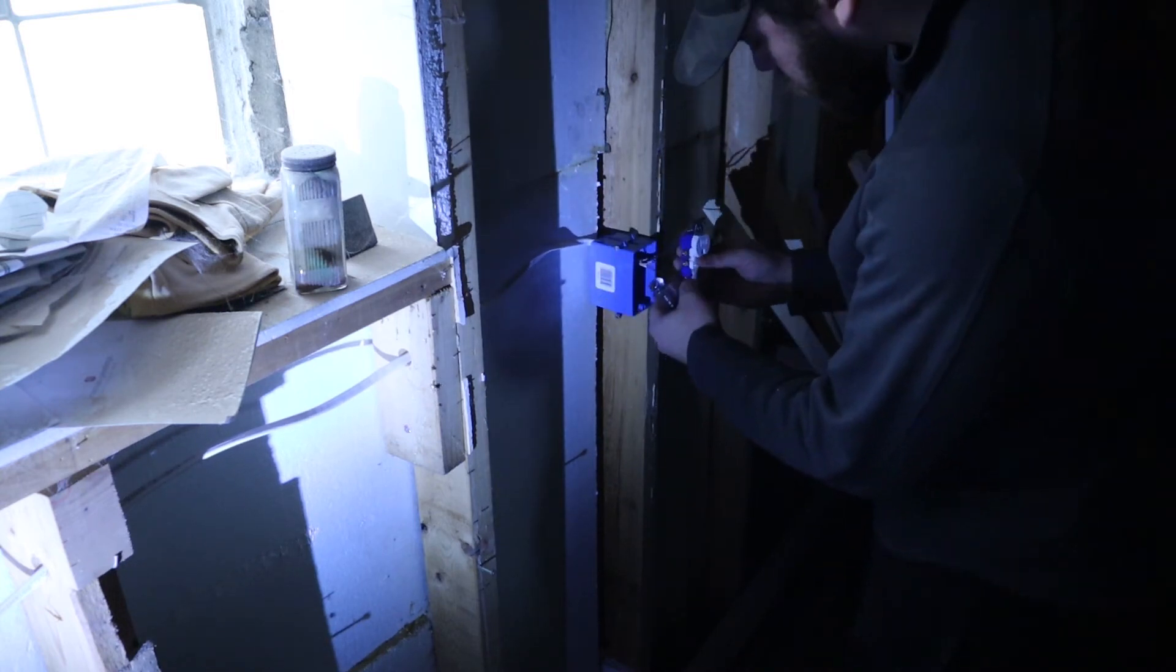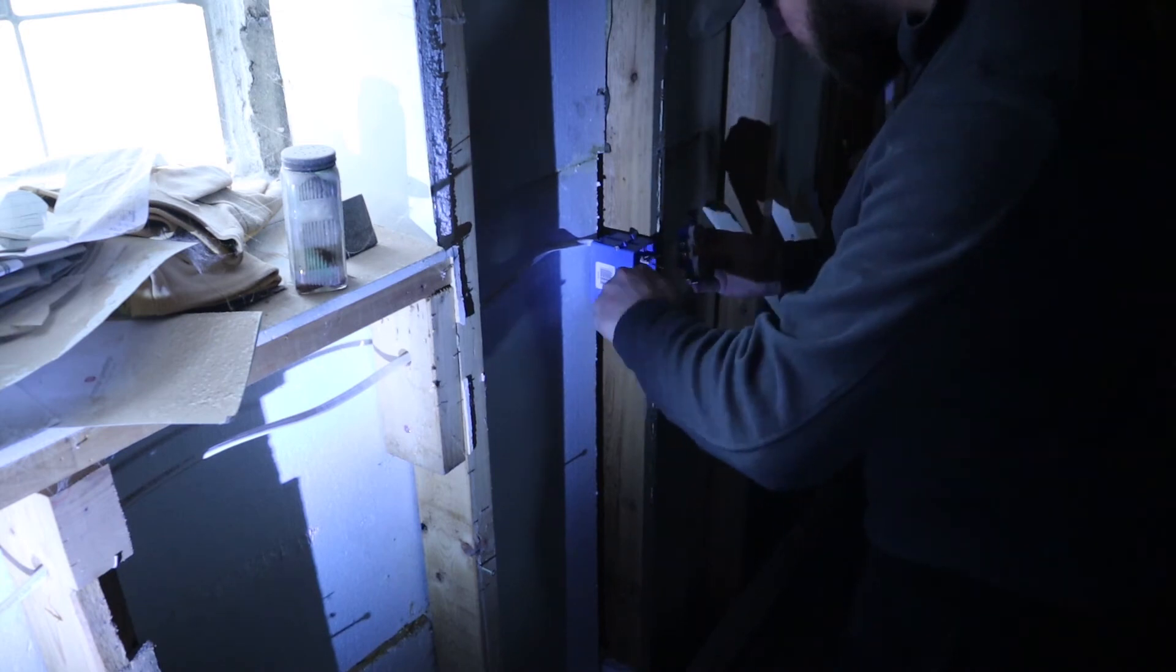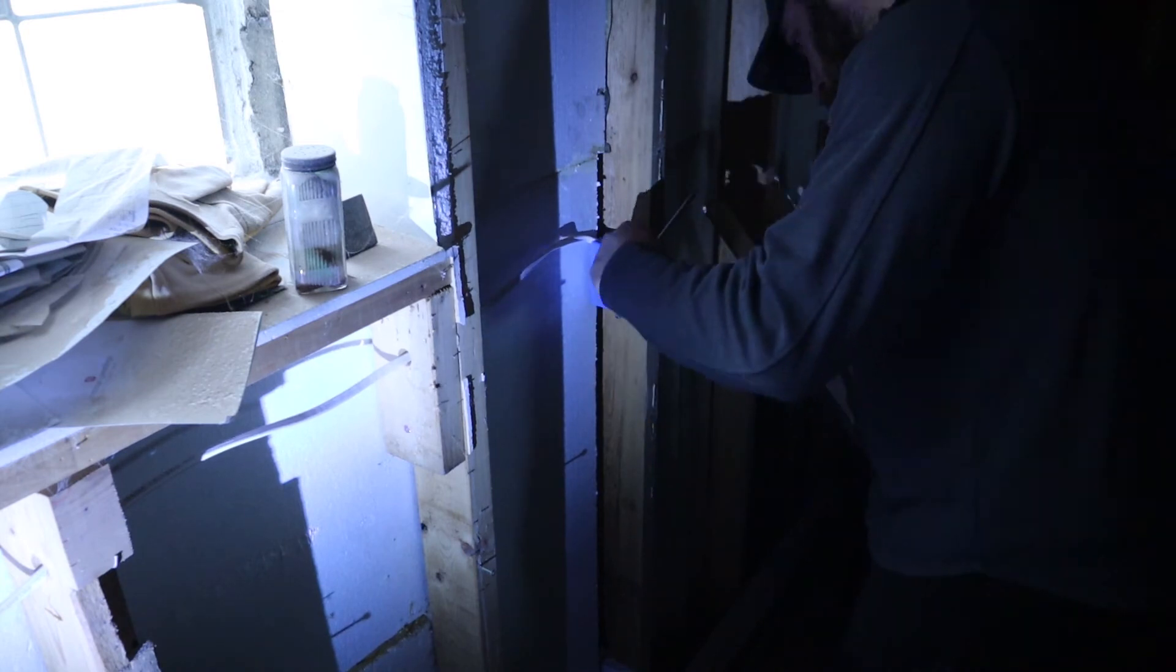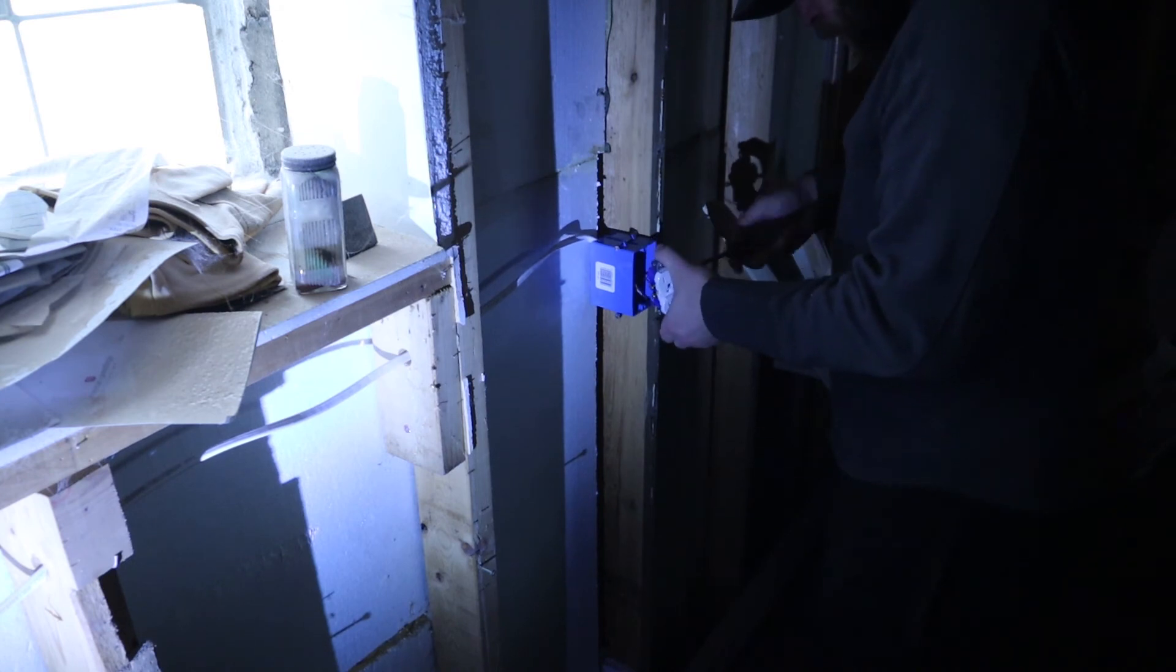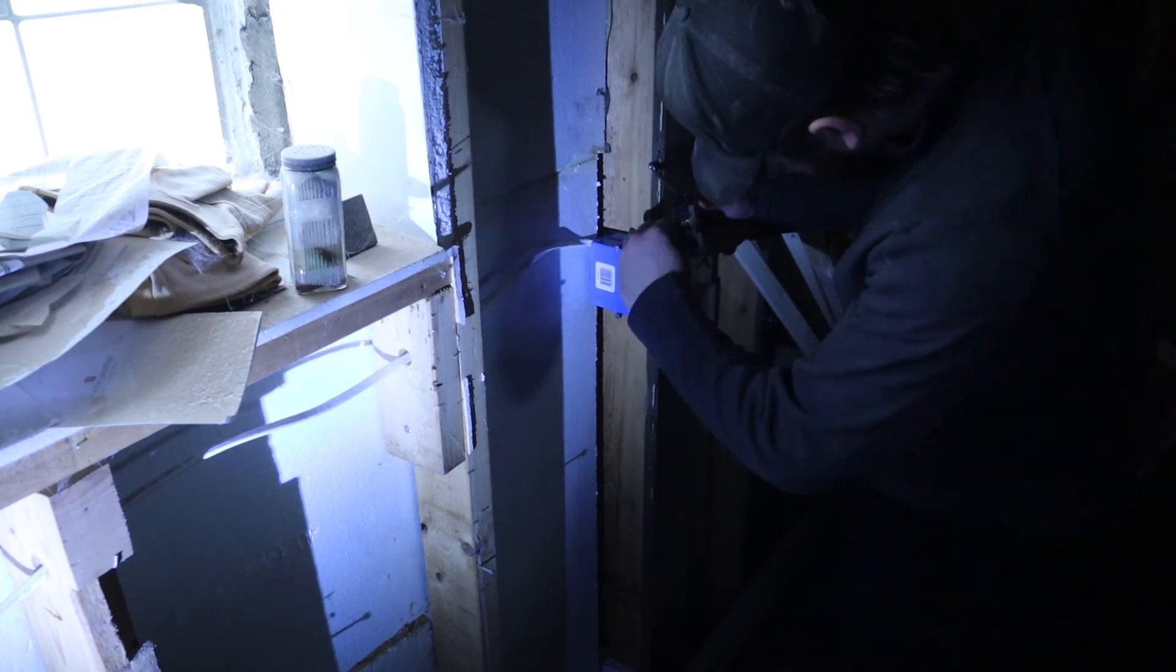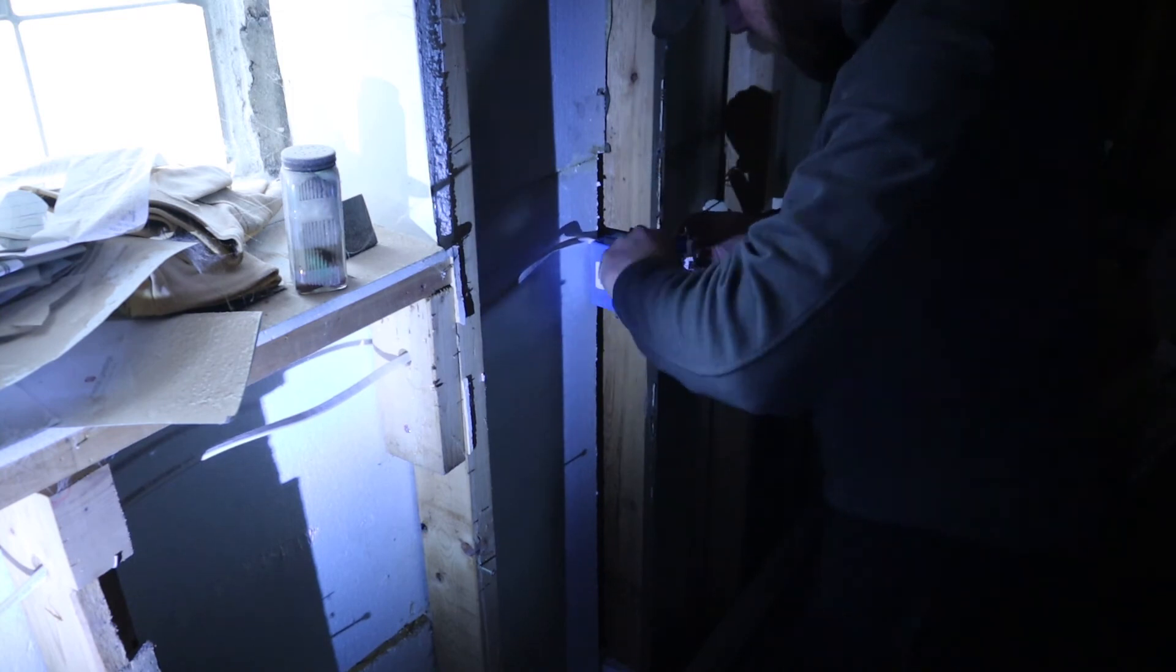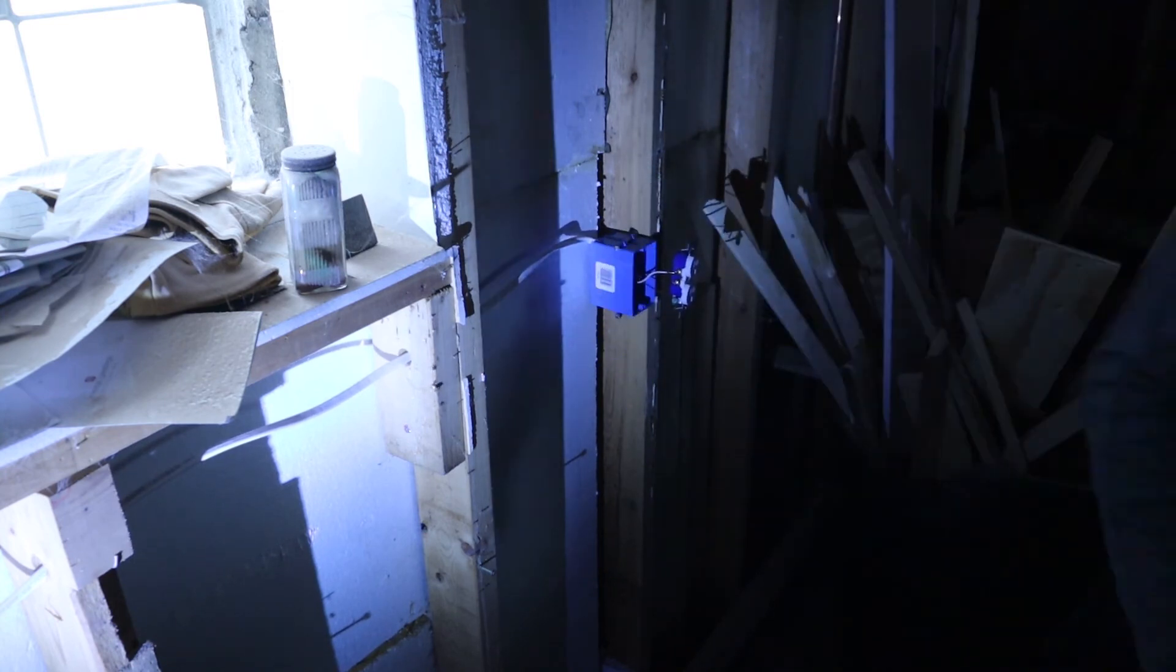And connecting the outlet I'm going to go through the same steps as I did last time. The only thing that I'm going to do differently is connect the ground wire to the green screw on the bottom. And I found it's easiest to do this first because it's the most out of the way wire. If you do the black and white first then you really got to stretch the ground to get to it.